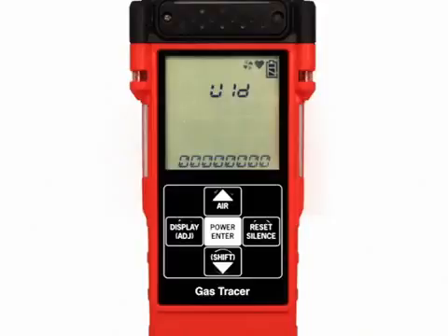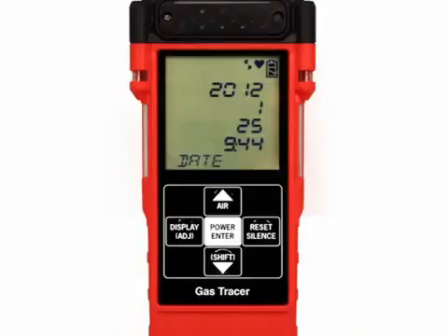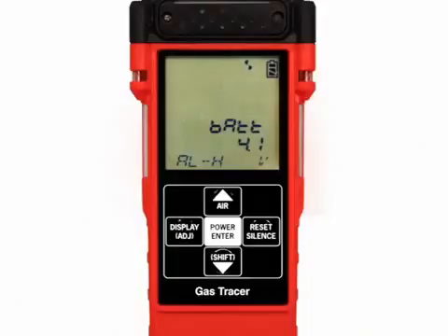If the ID display setting in maintenance mode is on, the user ID screen will appear for a few seconds. The station ID screen will appear for a few seconds. Once the normal startup sequence begins, you will see several screens indicating the status or settings of the instrument. The first screen is the date and time screen, which appears for a few seconds. Next, the battery voltage and alarm pattern screen is displayed. This screen displays the current battery voltage and the alarm logic.